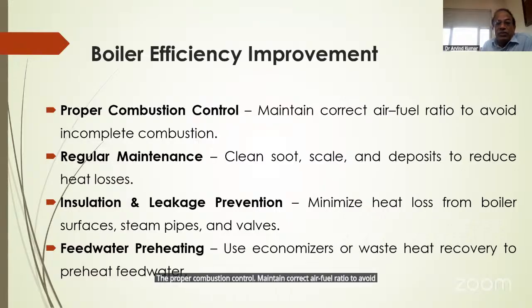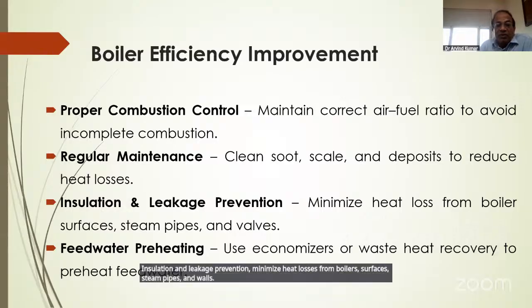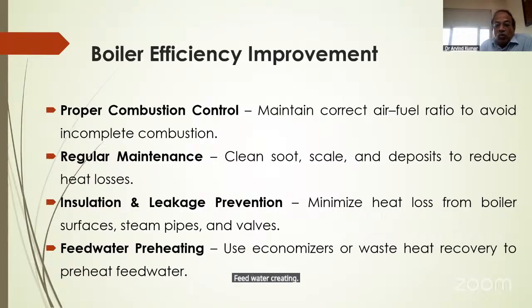avoid incomplete combustion. If there is any CO present in the exhaust gases, it will be detected in time, and we have to maintain the proper airflow for the combustion air-fuel ratio. Regular maintenance: clean soot, scale and deposits to reduce heat losses. Insulation and leakage prevention: minimize heat losses from boilers, surfaces, steam pipes and valves. Feed water preheating: use an economizer or waste heat recovery to preheat feed water.